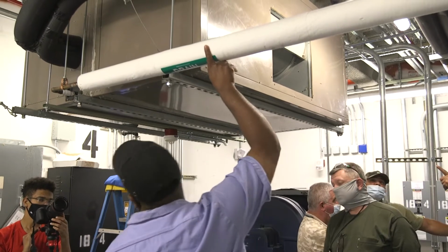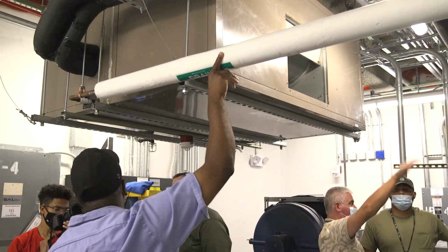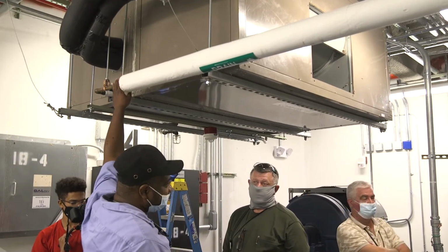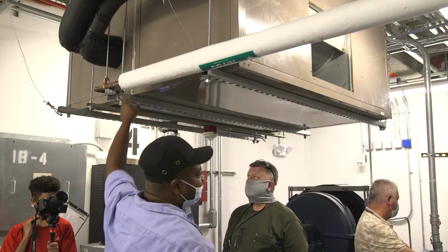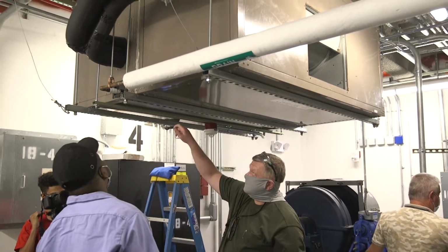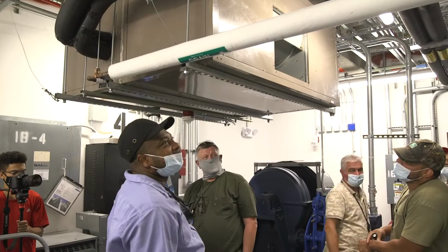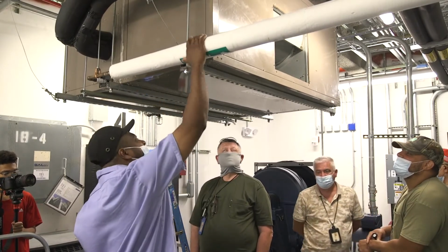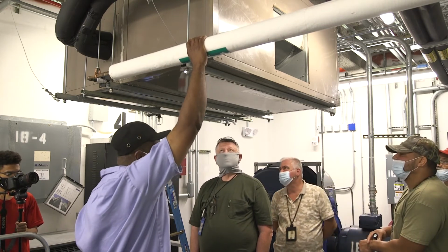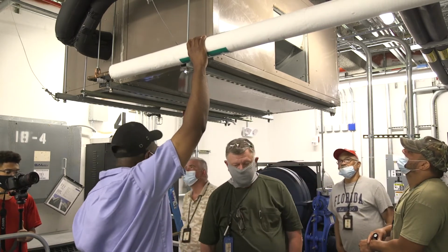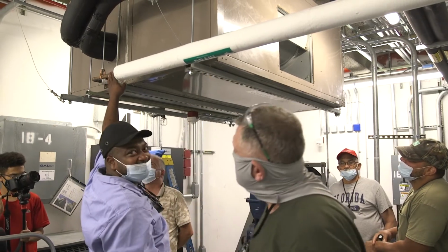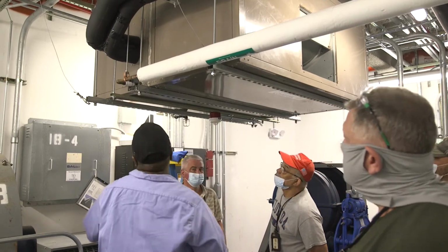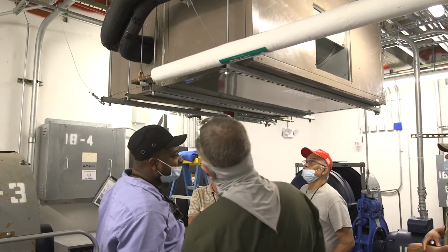This drain line should have been trapped, but it's not. Is there access over there to clean it, or how do we get to it? The installers would be the ones to let you know that. This is external to my unit, so this is all field installed. Like I said, this should have had a drain trap, and I already see it doesn't. It should have a U-trap.